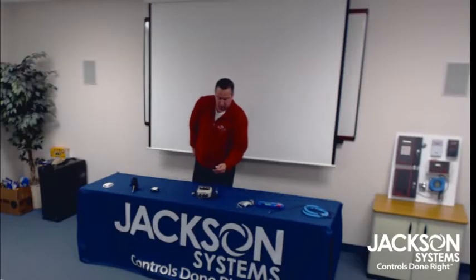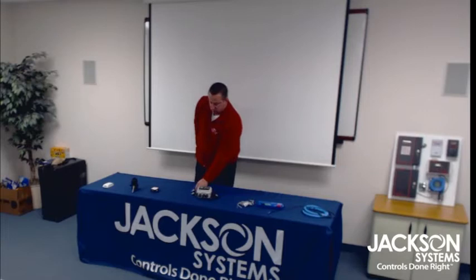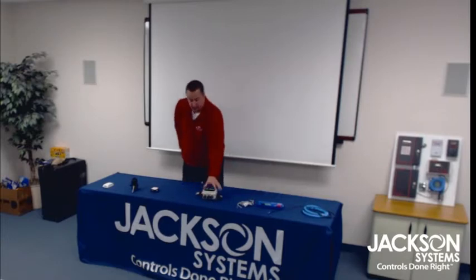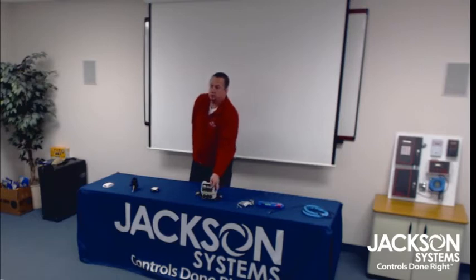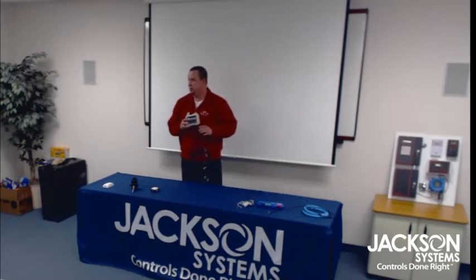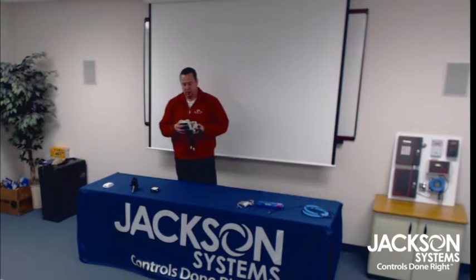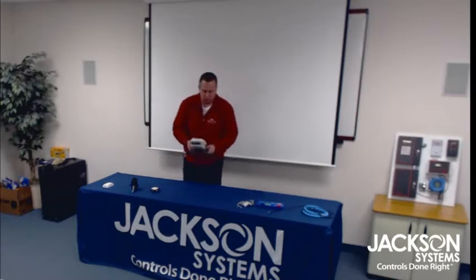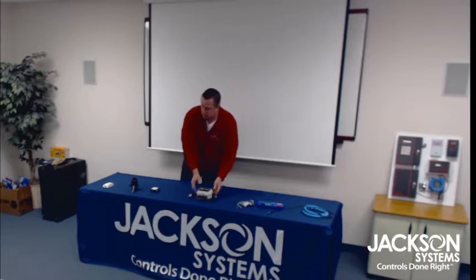One's labeled high, I should say, one is labeled low, so you know what sensor to put it on. And again, high and low on the cover. We also have a Dash 300 PSI, so the WPR 300, and that's jumper selectable up to 300 PSI. And its analog inputs and analog outputs are all jumper selectable: 0 to 10, 0 to 5, and 4 to 20 milliamp. So that'd be wet-to-wet differential pressure.